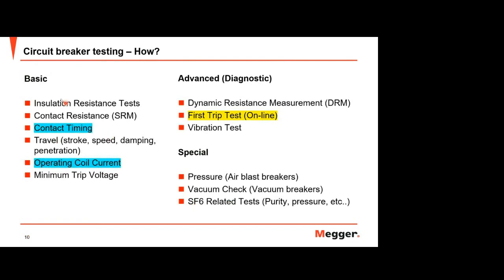And this is the circuit breaker testing. If you look at the standard testing of the circuit breaker, there are many tests that should be done to analyze your breaker correctly, from basic, advanced to special. In the basic testing, there are many tests to be done, like insulation resistance test, contact resistance, very common contact timing, travel, mostly for high voltage circuit breakers, and also operating coil current and minimum trip voltage. And as you can see here, the first trip test is part of the advanced diagnostic testing.